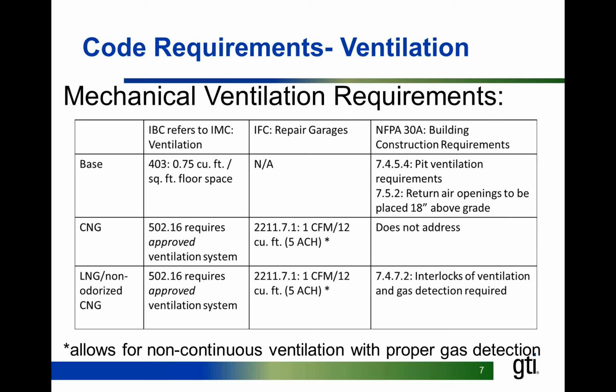A key to ventilation requirements is where that asterisk is in the middle. For the International Fire Code, it has an allowance so that you do not have to have continuous ventilation in a facility with natural gas, even a major repair area, as long as you have proper gas detection. And then the ventilation can be turned on as soon as the gas detectors sense that there's a harmful amount of gas in the area.